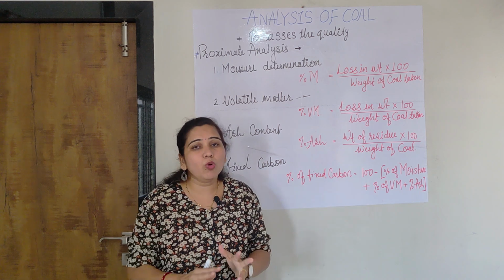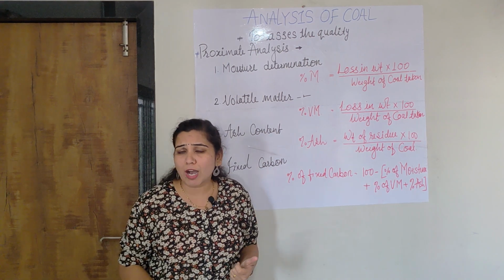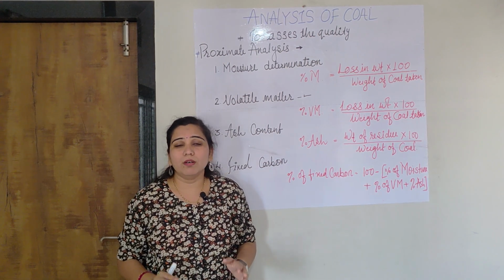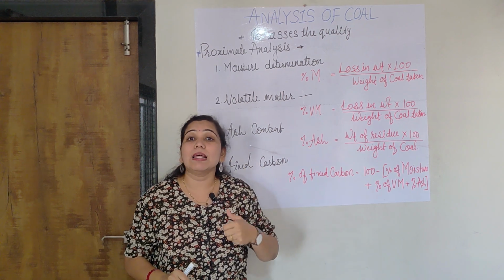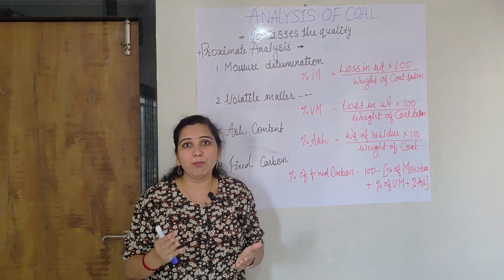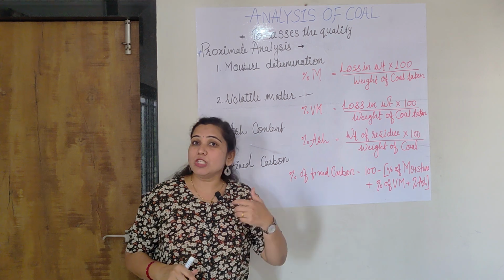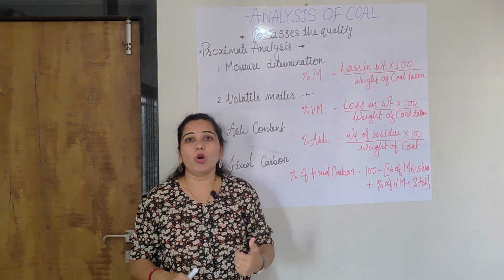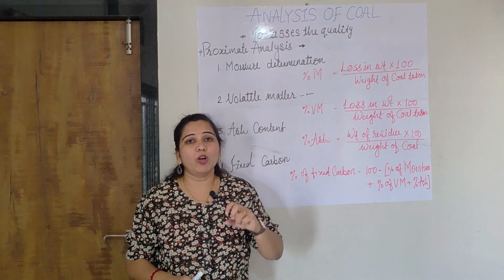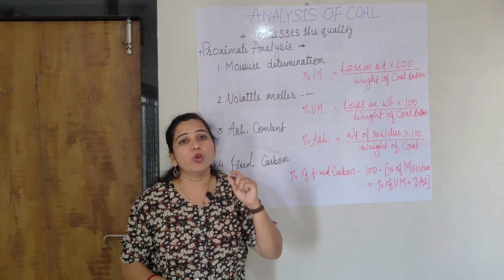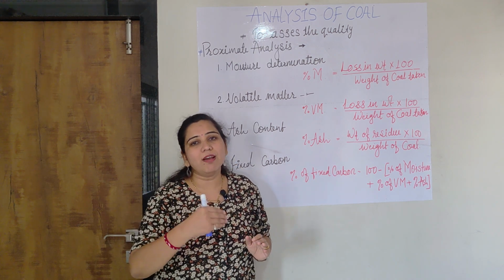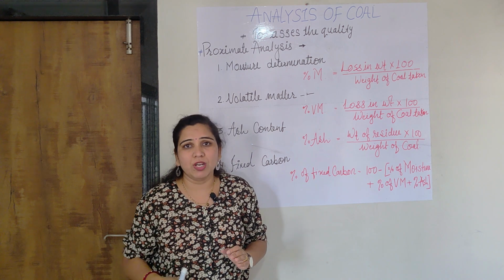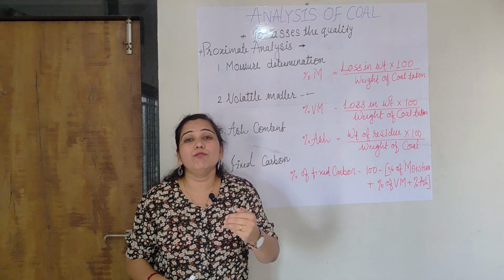Do all coals have the same composition of carbon? No. Because of this, we have to analyze the coal to know its composition according to its use. For example, if we want a very good quality coal, it must have the highest content of carbon, the lowest content of ash, and the lowest content of moisture.